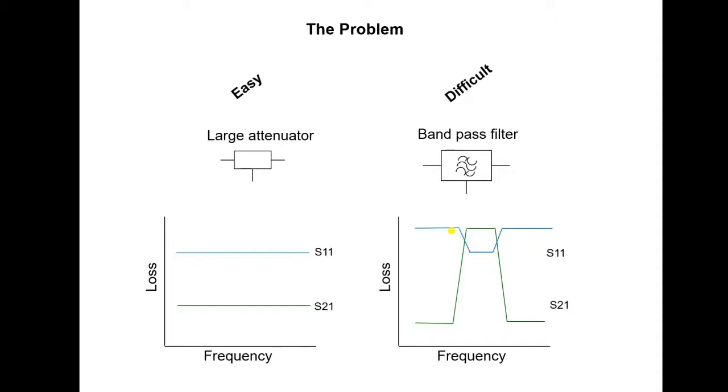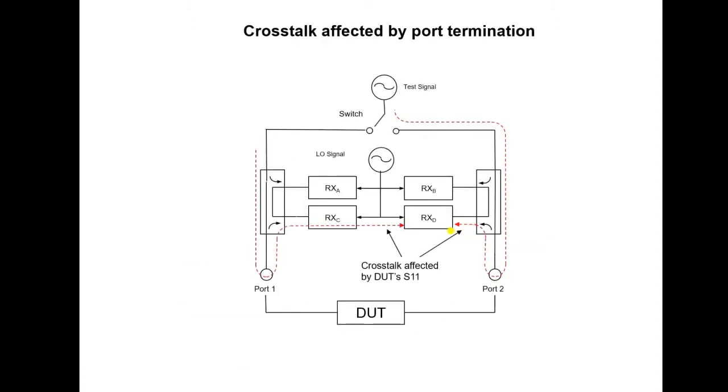Let's expand on that. Here, we have a simplified block diagram of the VNA. Assume we have a situation where we want to make a measurement in the forward direction. We have the forward reverse switch in the forward direction here, and the test signal is diverted to port 1.